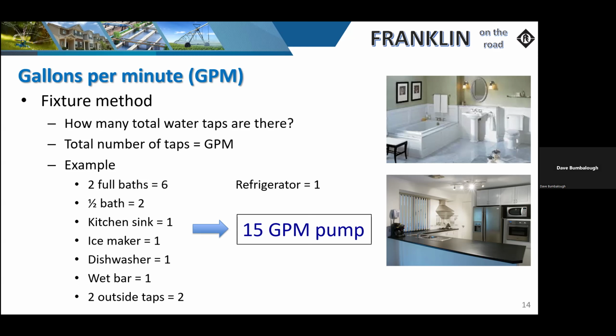So there's 2 fixtures. You go to the kitchen, you have a kitchen sink, you have an ice maker. Oh, I guess I did put that in there. There you go, ice maker and refrigerator. So we can scratch one of those off. But nevertheless, dishwasher, wet bar. As you can see, we've got a wet bar here. And what you don't see is out of the picture, there's a sink over on the other corner. And then outside, we have 2 outside taps. So as we add these up, we come up with 15 gallons per minute.